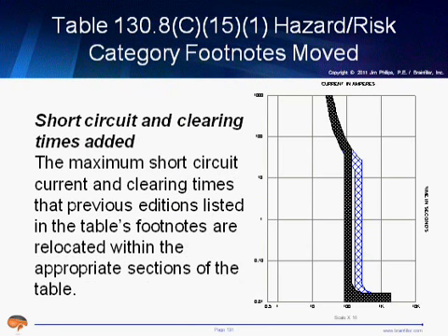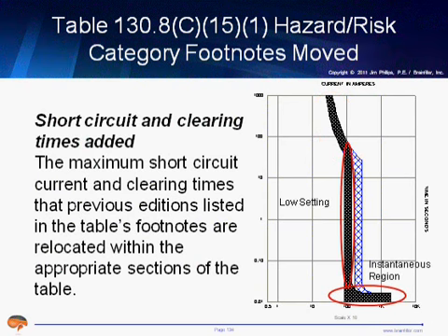The hazard risk categories, the footnotes that were at the bottom of the hazard risk categories, used to have limits, maximum short circuit current, maximum clearing time, and these footnotes are actually going to be embedded and be part of the tables, which I think is a great idea, because then you'll be able to look at your equipment, look at the task, and the limitations are right there. And the reason you have limitations, what I have on the screen is a time current curve of an adjustable molded case breaker. The upper part that I have circled is for overload protection for low-level currents. And then down towards the bottom, this is the instantaneous, fast-acting, fast operation. Some adjustable devices have low settings, as well as higher settings, as well as many settings in between.